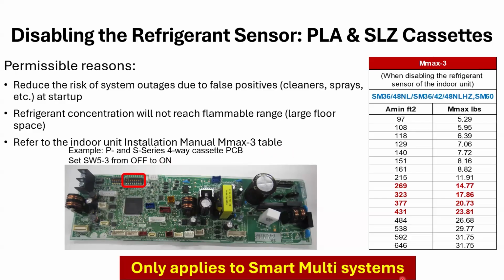So yeah, compare total charge to the room where the unit's going to be installed. And if it meets those requirements where you don't need the sensor and you want to disable it, then you can do that. To me, I would probably just leave the sensors active, not go through and try to guess, okay, we don't need to use this one because it is in a larger square footage area, and we do need to use this one, etc.